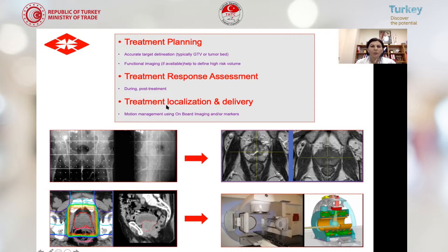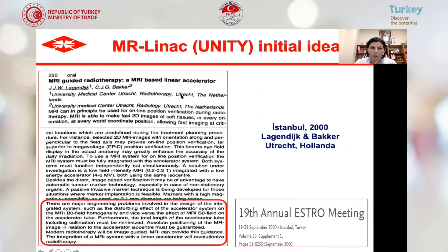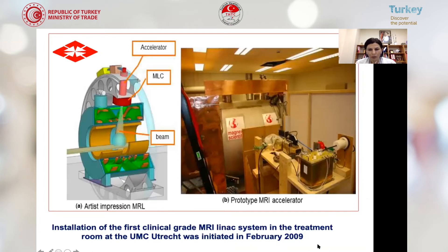During treatment response evaluation and during actual treatment delivery, imaging is needed to look at tumor localization. In every part of radiation treatment, we need qualified imaging. MR-LINAC Unity integrates all these goals together. It was initially proposed in the year 2000 at the 19th annual ESTRO meeting in Istanbul. The biggest challenge in MR-LINAC is using photons in a magnetic field, which was overcome in 2009.